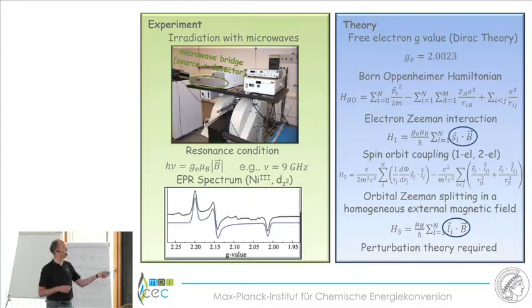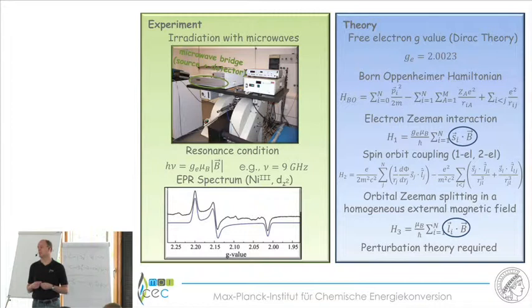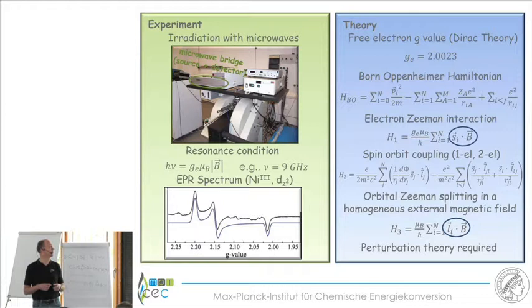This is a picture of a typical EPR spectrometer. The box on top is called the microwave bridge — the source where microwaves are generated, like the microwave oven of our spectrometer. It also contains the detector. The microwaves are led to the middle of the magnet where the sample is located. The sample can absorb and emit microwaves, which then go back into the bridge where we measure how many microwaves are coming back.